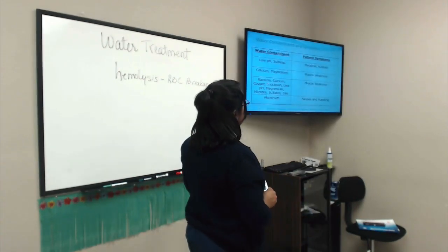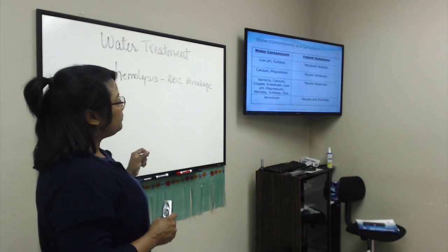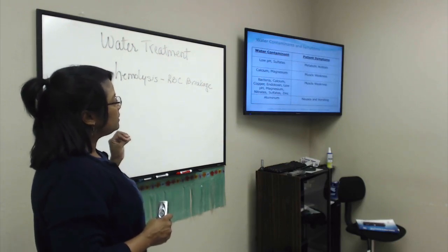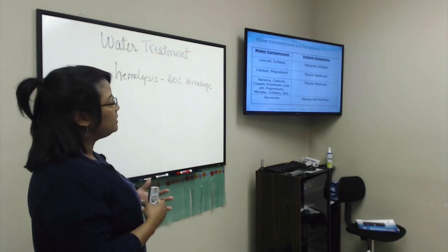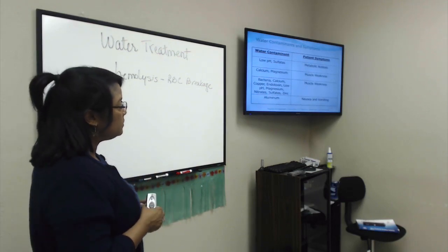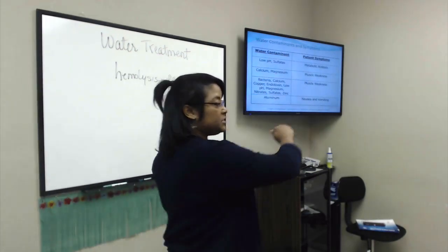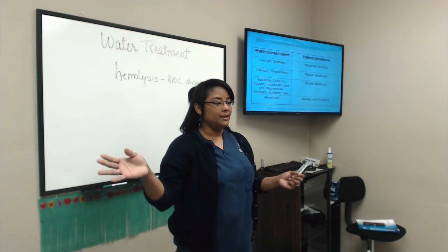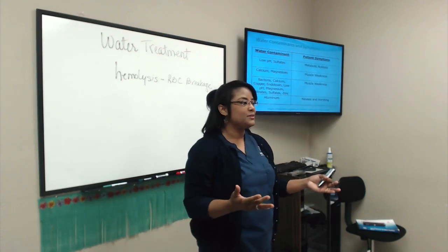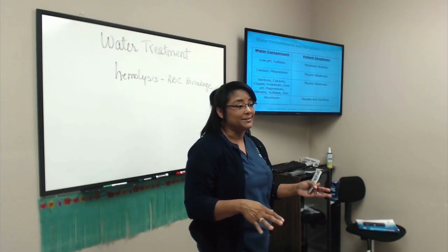Okay. Calcium, magnesium can cause muscle weakness. Bacteria, calcium, copper, endotoxins, low pH, magnesium, nitrate, sulfate, zinc can cause muscle weakness too. And aluminum can cause nausea and vomiting. If all the patients from that side all of a sudden start vomiting, water. Just turn it off, turn off the machine. Even if you're not sure.